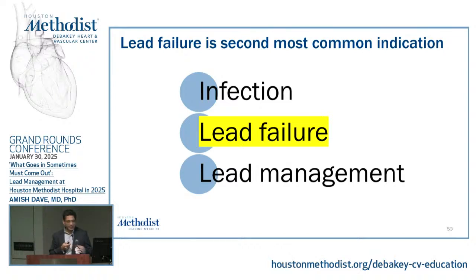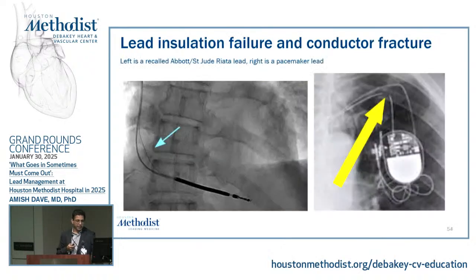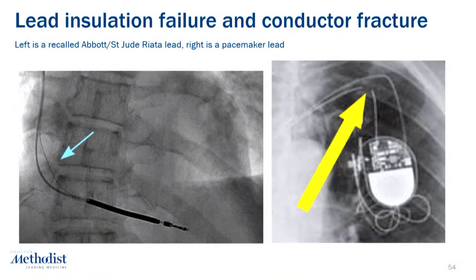Now we'll talk a little bit about lead failure. Basically, this is another indication. There are many types of failures. They basically fall into an insulation problem of the lead or a fracture of the conductor. And sometimes this is very obvious. The St. Jude or Abbott Riata lead has a Class 1 FDA recall, because the conductors can actually come out of the outer insulation, and that can lead to noise and over sensing of noise, leading to inappropriate shocks and actually VT storm.